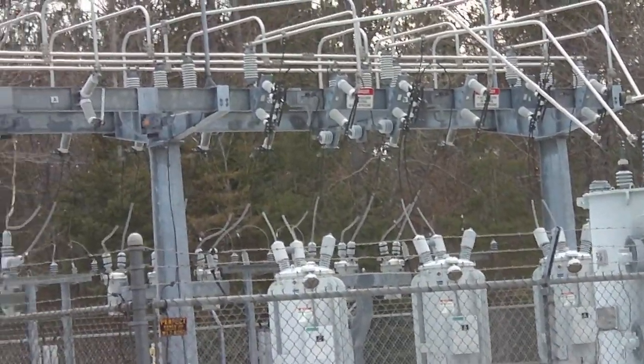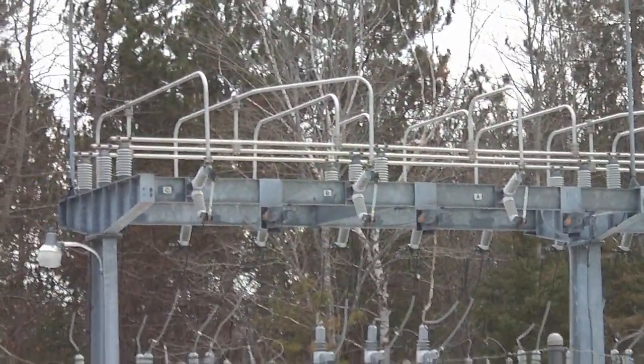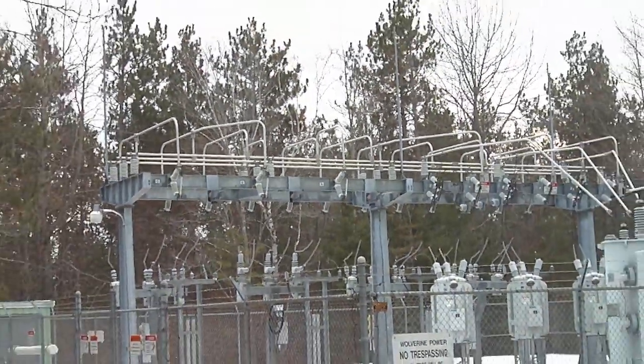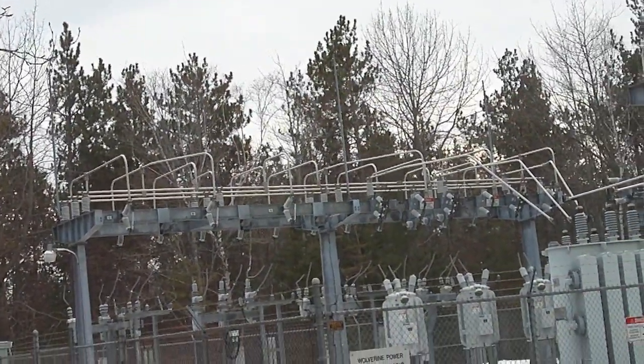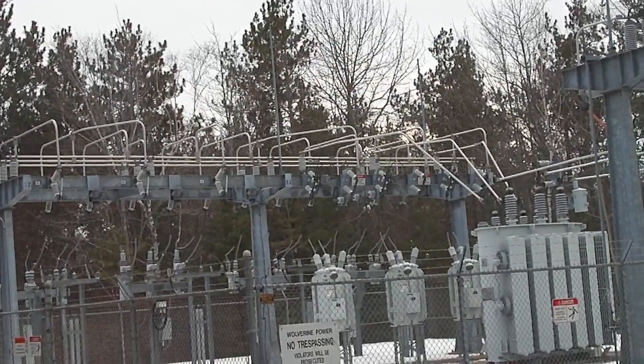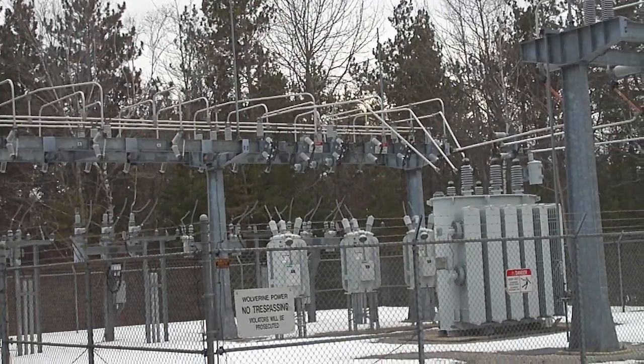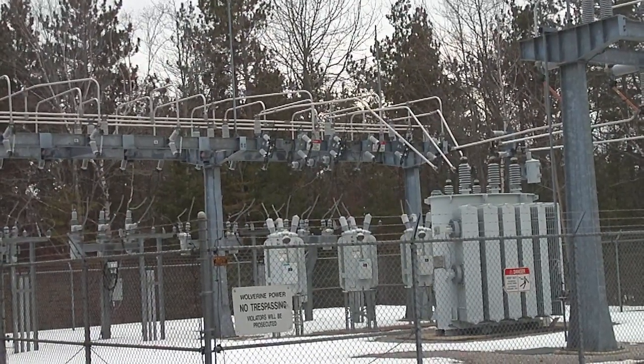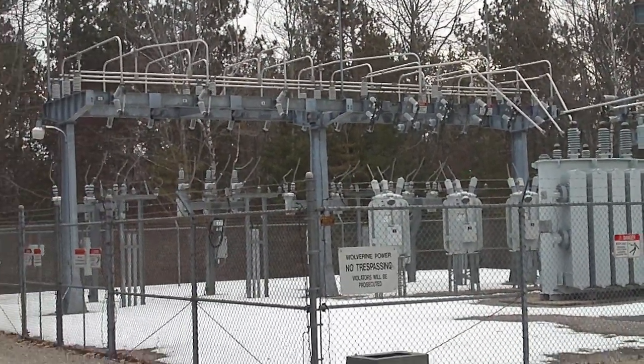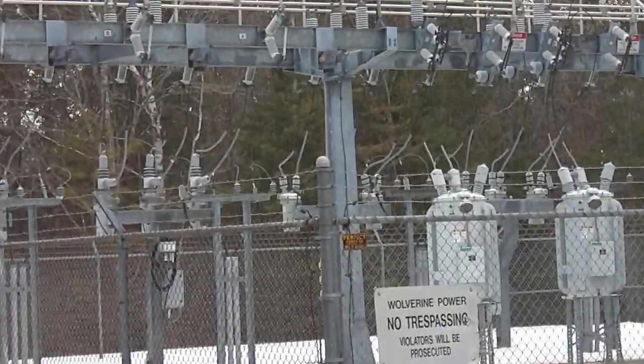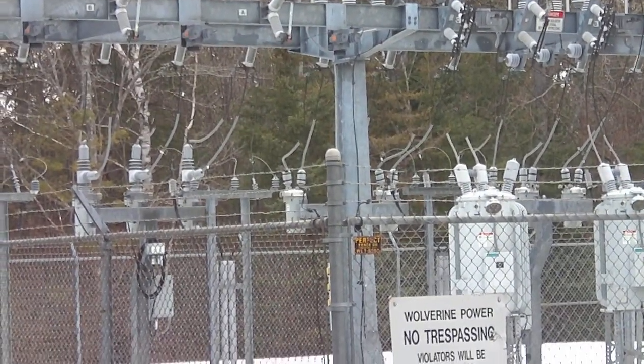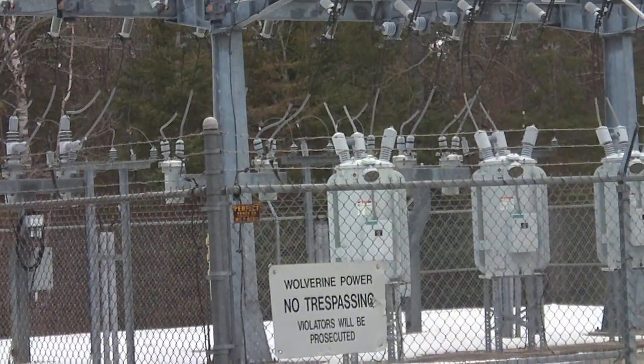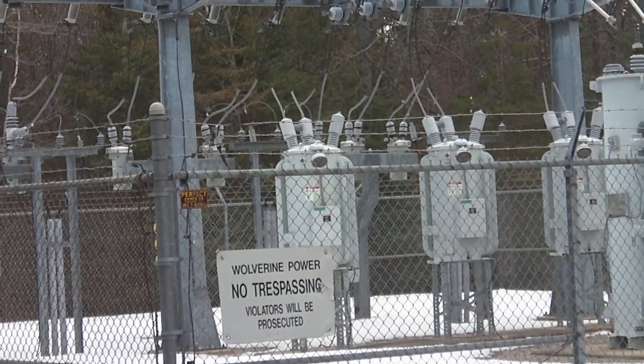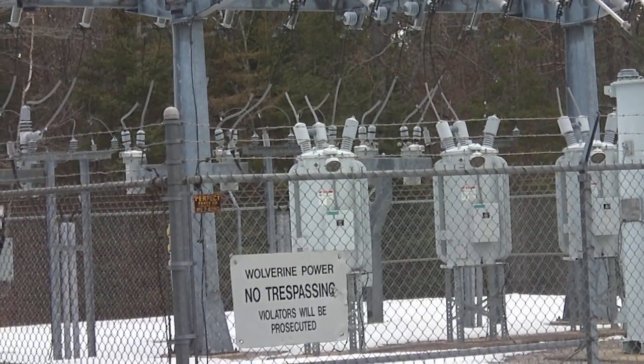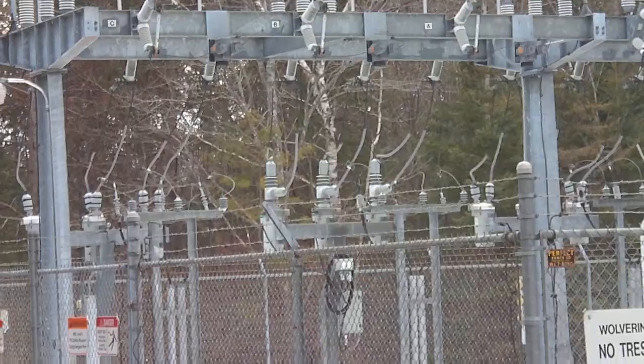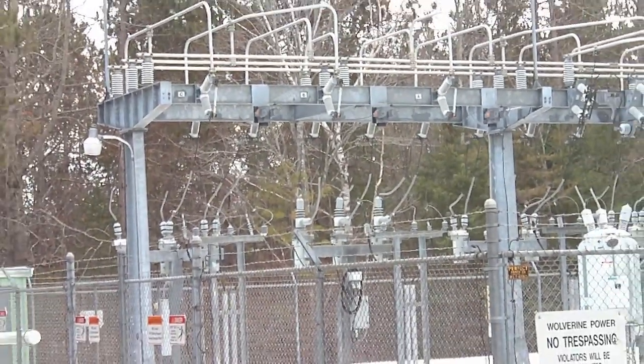Now notice all the tubing that's up there. Those are actually all the conductors. Instead of running wire in substations, a lot of times they run tubing. On the back side of that superstructure, you will see some of the station arresters, and in the back you're going to see these reclosers, some of the protection scheme for the secondary circuits. Now, Grand Lake Substation has three active secondary circuits coming off of that. There's room over on this side to add a little bit more.